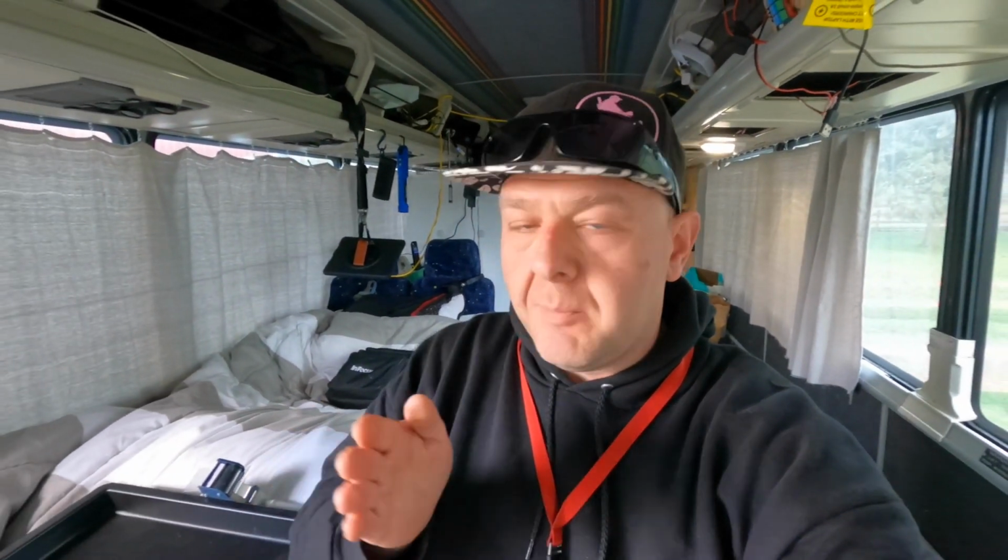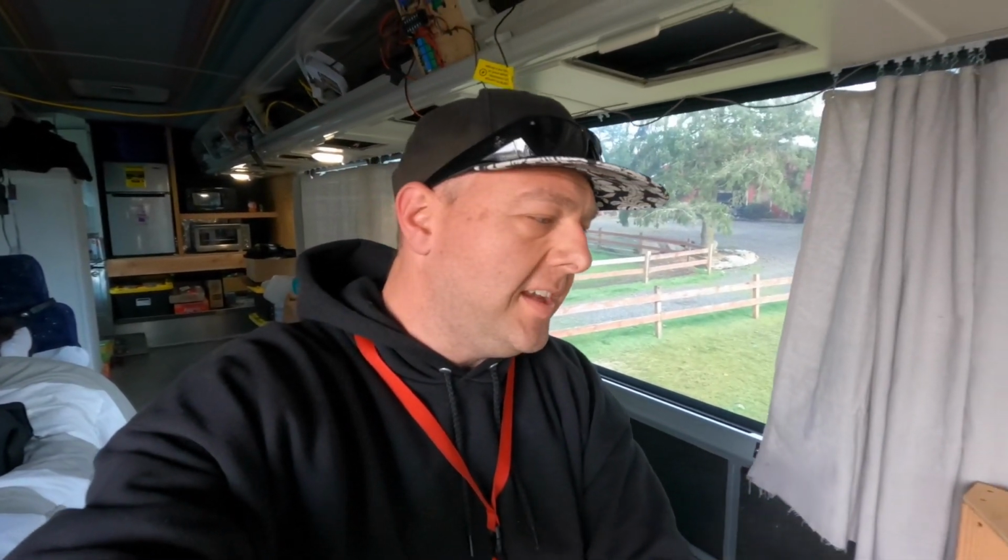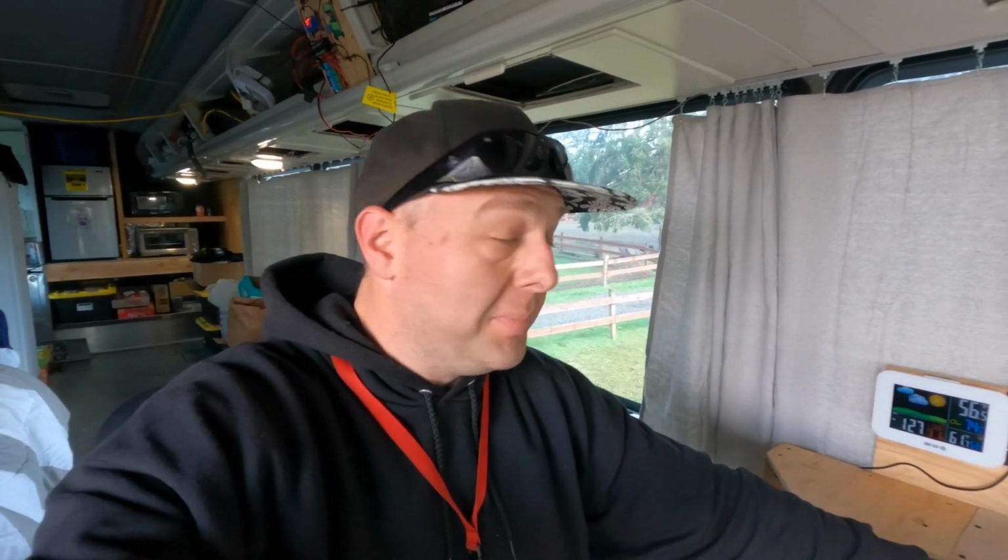Sweet. Oh, I just thought, since we have this thing fired up, I'm gonna move it over a little bit so I can get to the battery bay on this side. This inverter has a battery charger built in, and I couldn't find any documentation. I tried chatting with the people that built it or sell it, and they can't tell me what the difference between the bulk charge voltage and the float voltage is, which is very important with these Odyssey batteries. If you charge them at too low a voltage, it severely shortens their service life.